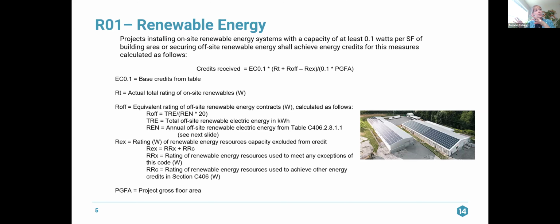It's interesting, this calculation was updated in the Model Low Energy and Carbon Code. Under the 2024 IECC, any renewables that you are using to comply with Section C405.15, the mandatory on-site renewables section, have to be removed from this calculation. So you can't count those renewables that you're using to comply with the base code towards your additional renewable and load management credits. This is the Model Low Energy and Carbon Code version of the calculation. The credits received equal the base credits from the table, EC 0.1, times RT, which is the actual total rating of on-site renewables in watts. That's important. I tried to do this in kW before I really read through the calculation, and it obviously didn't work. So it has to be in watts.